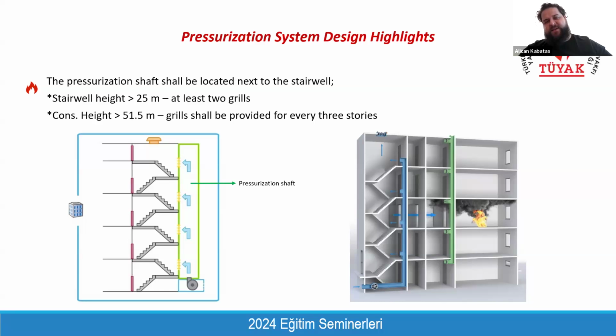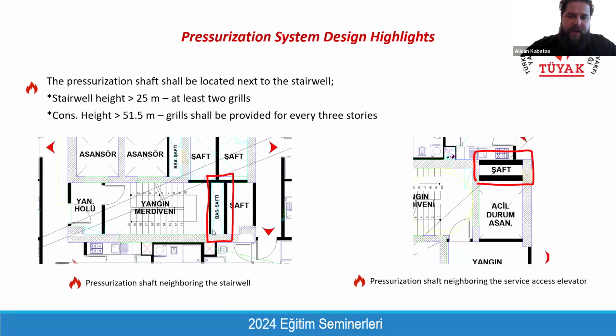we need to have a pressurization shaft, and this shaft should neighbor the fire escape stair, because the pressurization shaft is a part of the fire escape stair. It should be considered as an extension of the fire escape stair.